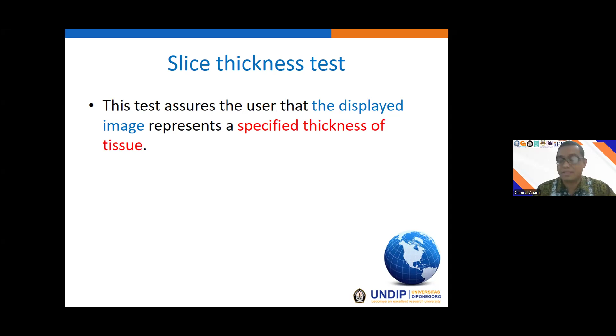This is the IAEA standard for the image slice thickness or the image slice width. The standard is 0.5 millimeters for slice thickness less than 1 millimeter, within 50% for slice thickness from 1 to 2 millimeters, and for slice thickness above 2 millimeters, the slice thickness should be within 1 millimeter. It is based on the IAEA standard.